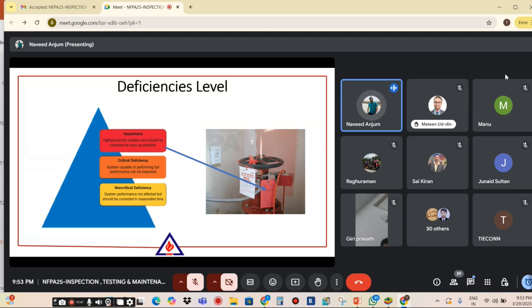Then a critical deficiency is where the system is capable of performing, but performance can be impacted. Like there is some leakage in the system. Because of the leakage, the system may not perform as per requirement. So we have to correct it, and it is a critical deficiency. And the third one is impairment, the highest priority problem, which should be corrected as soon as possible. Like if our valve is completely blocked, it is an impairment. We have to correct it on a priority basis. So we will use our red tag for this type of impairment.